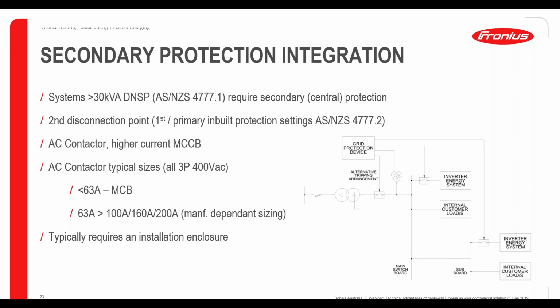That's typically done through devices such as AC contactors, usually for low currents. If the currents get higher, typically motorized circuit breakers are deployed. What's important to realize here is that contactors are typically split in two categories, smaller than 63 amp and higher than 63 amp, and they all require enclosures to be installed. Smaller contactors are much easier to install, commission, and I'd say troubleshoot as well. If we go to the next slide, we'll actually see what we're trying to communicate here.